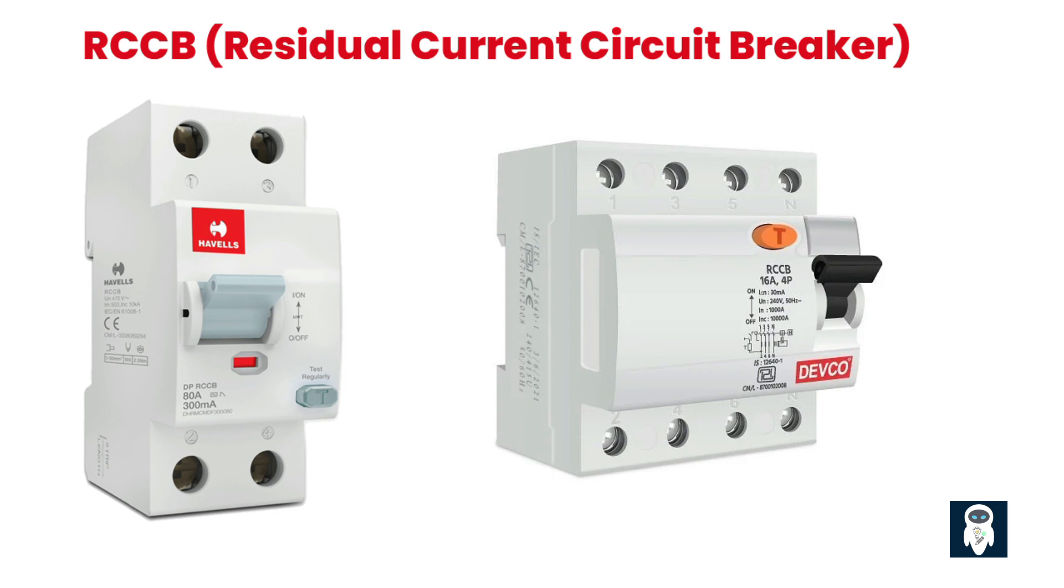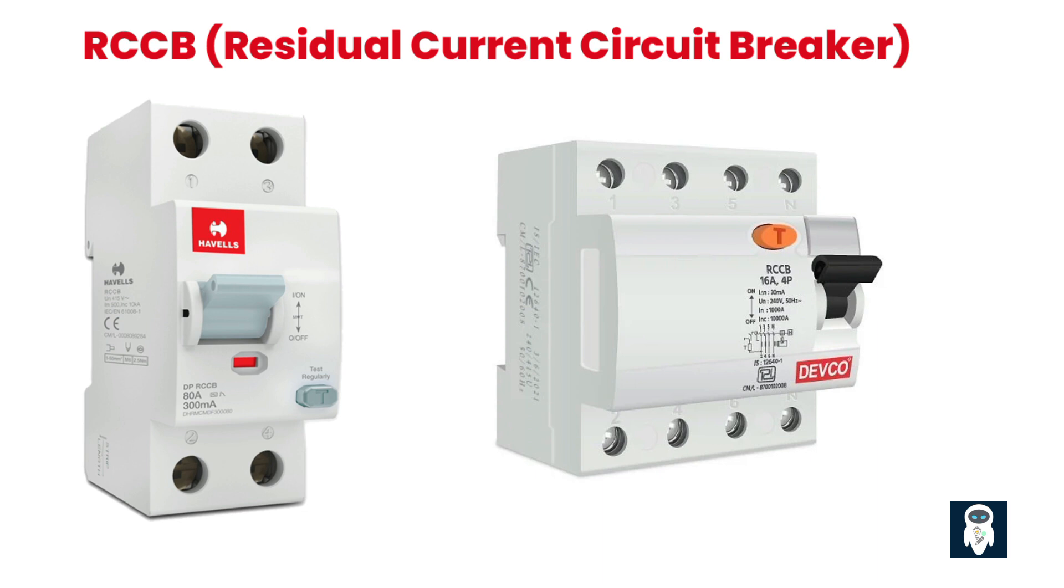RCCBs are also commonly referred to as RCDs, Residual Current Devices, or GFCIs, Ground Fault Circuit Interrupters, in some regions. The primary function of an RCCB is to detect and interrupt the flow of current when there is a leakage or imbalance between the live and neutral conductors. It provides protection by monitoring the difference in current between the outgoing and incoming conductors of an electrical circuit.